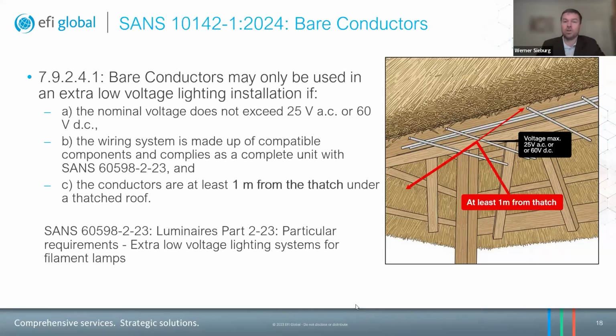It's fine if those conductors are non-insulated. I think of an art gallery, for example, where the lamp connects to both these bare conductors, and the lamp then sources from the live and the neutral and illuminates the room. So such bare conductors, obviously there is a human safety aspect to it, but today we're addressing specifically the fire risk. So they may only be used in an extra low voltage lighting installation.